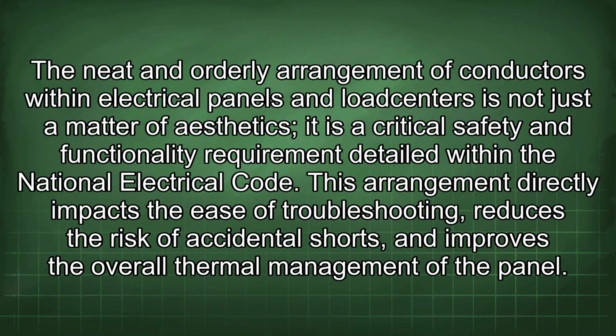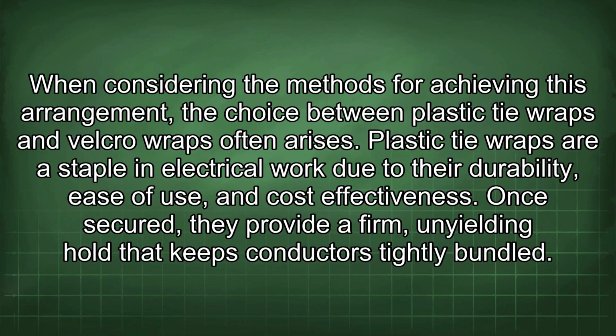The neat and orderly arrangement of conductors within electrical panels and load centers is not just a matter of aesthetics, it is a critical safety and functionality requirement detailed within the National Electrical Code. This arrangement directly impacts the ease of troubleshooting, reduces the risk of accidental shorts, and improves the overall thermal management of the panel. When considering the methods for achieving this arrangement, the choice between plastic tie wraps and Velcro wraps often arises. Plastic tie wraps are a staple in electrical work due to their durability, ease of use, and cost-effectiveness. Once secured, they provide a firm, unyielding hold that keeps conductors tightly bundled.